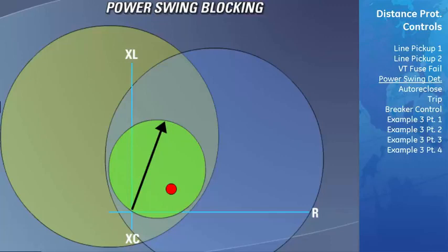The power swing blocking characteristic must therefore be configured to be much larger than the distance Zone 1 area of protection to ensure a stable power swing is detected well before Zone 1's operating characteristic is reached. The D60 has power swing blocking and out-of-step tripping capabilities as part of the power swing detect function. In this course, we'll only refer to power swing blocking.